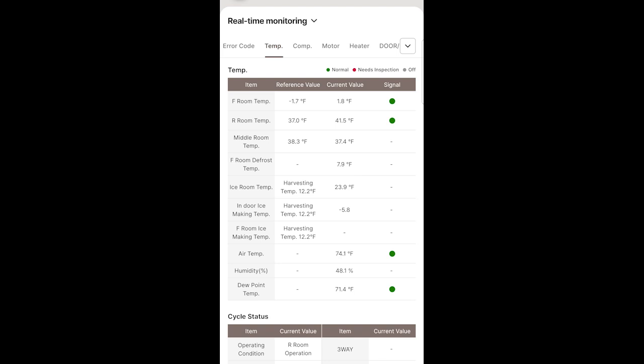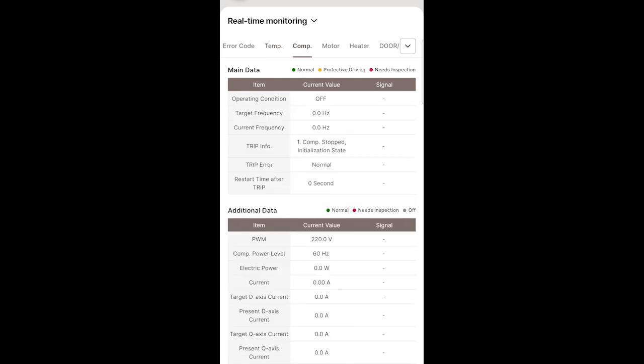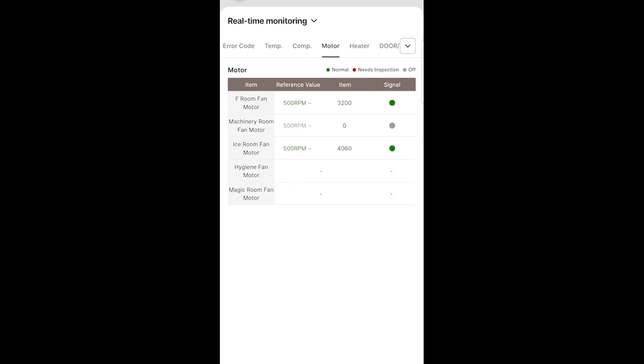It's a little bit high because I've had the refrigerator doors open while connecting. It gives us some stats off of our compressor and how it's running, and lets us look at our fan RPMs. It's saying 500 RPMs or above is the target, and under item it's telling you what the freezer fan and ice room fan are actually running at right now.